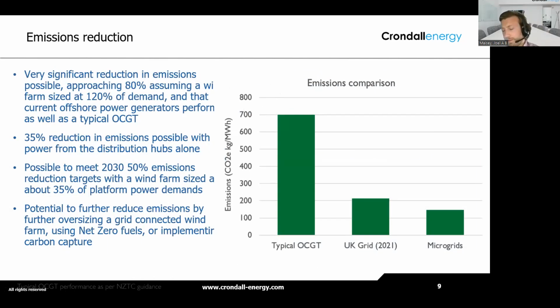The bit that's really important with these microgrids is, how much are we reducing emissions by? What we have here on the right-hand side is the emissions comparison. The units of the intensity are kilograms of CO2 equivalent per megawatt hour. And what you can see here is that for a typical offshore simple cycle gas turbine, we're emitting around 700 kilograms per megawatt hour. A microgrid reduces those emissions by around 80%, so we're down at around 150 kilograms per megawatt hour. And that's assuming we have a wind farm sized to around 120% of demand.